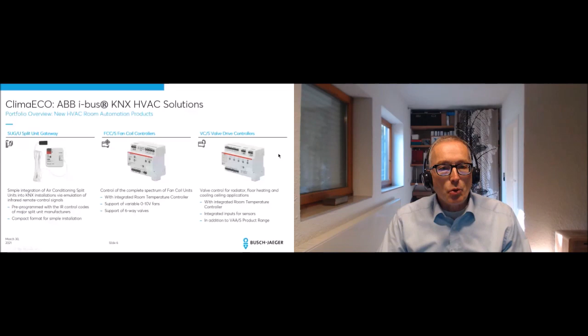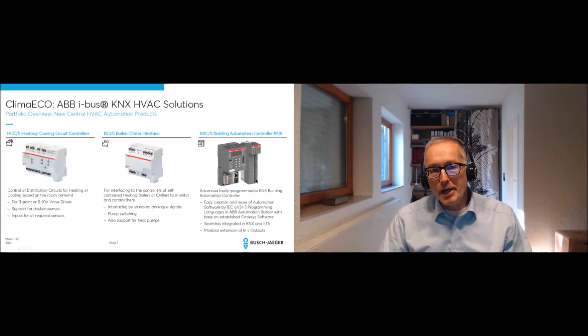Heating cooling circuit controller, I will talk about this a bit later as well, just for distribution, boiler chiller interface. And here you see not a typical KNX device. This is a building automation controller just for integrating a powerful PLC into KNX. And then, in my opinion, the heart of the system, the application controller, a pure KNX device, again here, with different functions. You will see later what's behind.